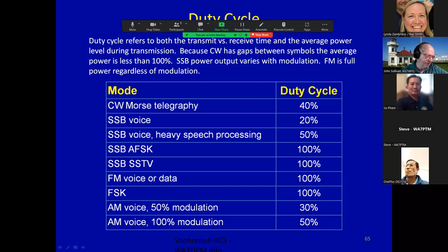Okay. So the FCC averages the RF exposure over time. They look at 10 and 30-minute periods, and these graphs kind of illustrate that. The vertical axis is the power level, and time is across the horizontal axis. The shaded areas in here represent the actual RF exposure. So a lower power level over a longer period of time might equal a higher power level over a shorter period of time. So it's the total exposure that we're looking at. As power or duty cycle increases, exposure time must be decreased. As the power or duty cycle is decreased, your exposure time can be increased, and yet you'd still have the same exposure level.